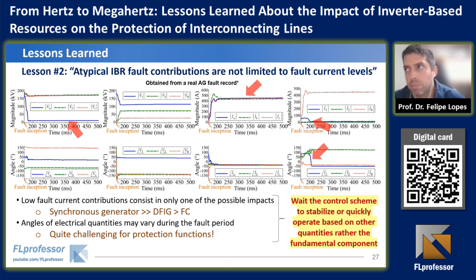And recently, it was confirmed in the IEEE standard, I think in section F.6, when they say that the underreaching element should be reliable when its settings consider the IBR response time, or when they write that the control system of an IBR may need some response time. And also, use of supervisory overcurrent thresholds and time delays may improve the protection system, or even backup protection may include application of time-delayed step distance zones. So we are talking about intentional delays, and people in Brazil are using this recommendation a lot.